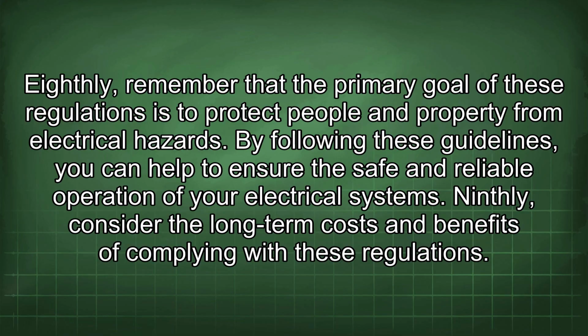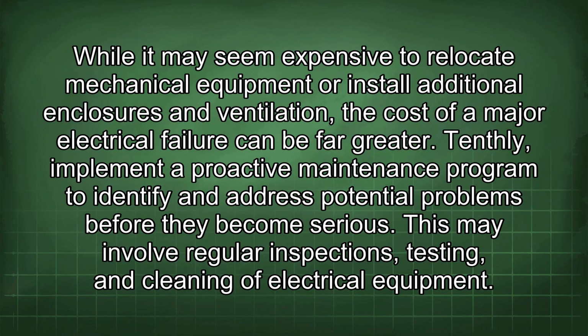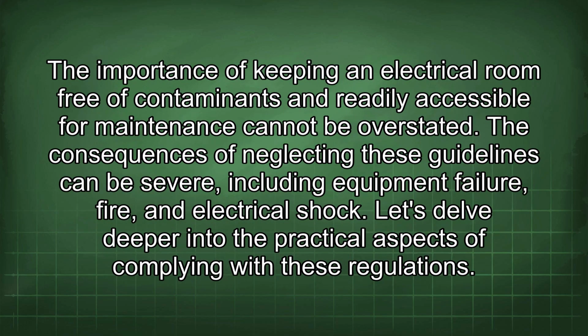Ninthly, consider the long-term costs and benefits of complying with these regulations. While it may seem expensive to relocate mechanical equipment or install additional enclosures and ventilation, the cost of a major electrical failure can be far greater. Tenthly, implement a proactive maintenance program to identify and address potential problems before they become serious. This may involve regular inspections, testing, and cleaning of electrical equipment. The importance of keeping an electrical room free of contaminants and readily accessible for maintenance cannot be overstated. The consequences of neglecting these guidelines can be severe, including equipment failure, fire, and electrical shock.